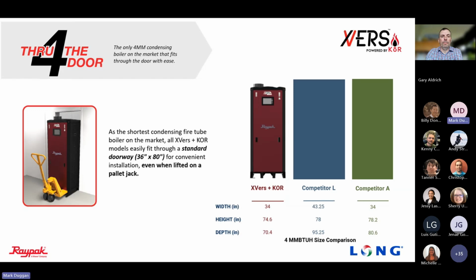The nice thing about that from a service and replacement standpoint, once you get that old boiler torn out, you don't need to tear out any doorways or walls or driveways or anything, whatever it may be, to get that boiler in the room. We've got holes for a pallet jack on the front, holes for a forklift on the side for easy job site transportation. But being able to just slide that boiler in through a standard doorway without tearing anything apart is a huge benefit from a service and replacement standpoint.